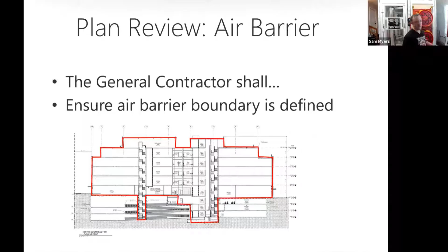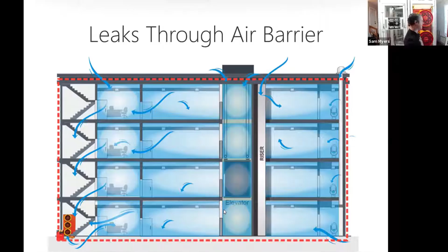This is a good diagram showing the general outline of how some of these buildings work. Usually you'll have a stairway column going up, with doorways to the stairs that you'll have to prop open. Sometimes you'll run tubing through these stair pathways to access and confirm that all parts of the building meet the desired test pressure. Same with the elevator shafts -- do you have to set an elevator car halfway in and halfway out, or is there a way to move it to drop cords and tubing down faster to reach your test center? These are all things to consider before test day.